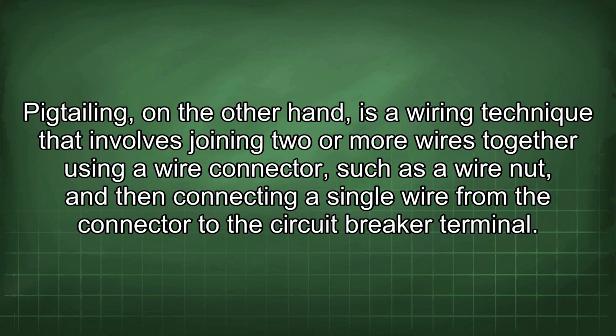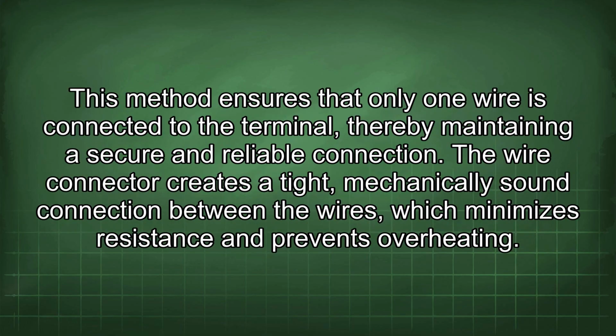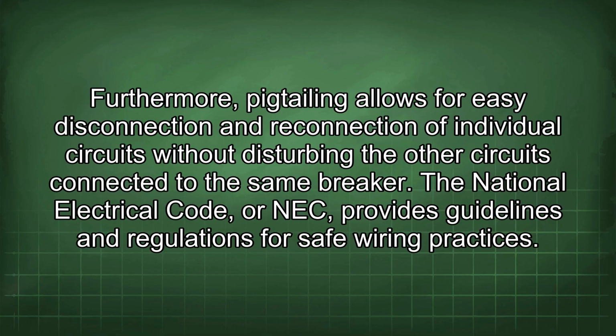Pigtailing, on the other hand, is a wiring technique that involves joining two or more wires together using a wire connector, such as a wire nut, and then connecting a single wire from the connector to the circuit breaker terminal. This method ensures that only one wire is connected to the terminal, thereby maintaining a secure and reliable connection. The wire connector creates a tight, mechanically sound connection between the wires, which minimizes resistance and prevents overheating. Furthermore, pigtailing allows for easy disconnection and reconnection of individual circuits without disturbing the other circuits connected to the same breaker.